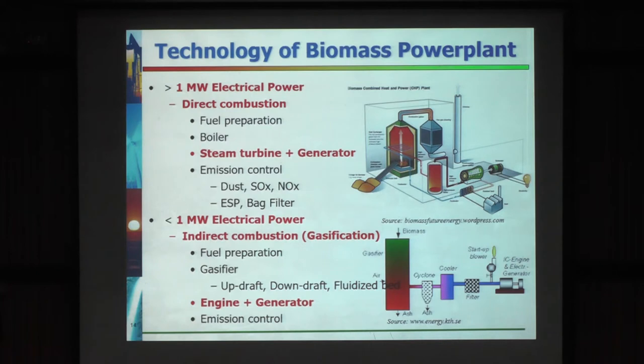For emission control for direct combustion, we also need to control the dust, SOx and NOx, by using different kinds of air pollution control equipment, such as the electrostatic precipitator to control the dust, and the bag filter also to control the dust. So almost all of the emissions that we control from these biomass plants are dust, SOx, and NOx. This is for the bigger power plant, which has a power of over 1 megawatt.